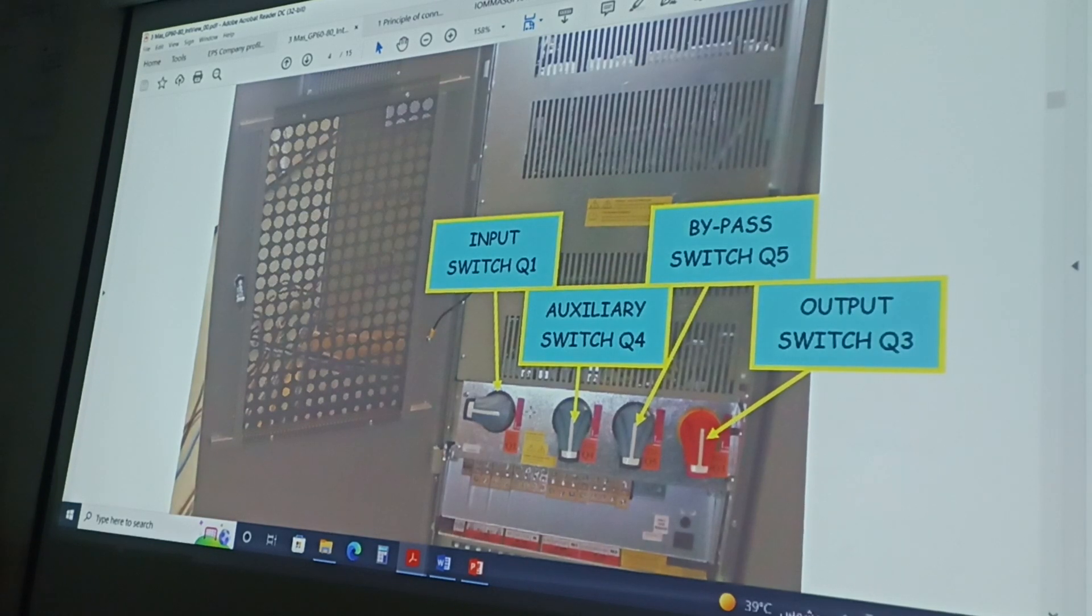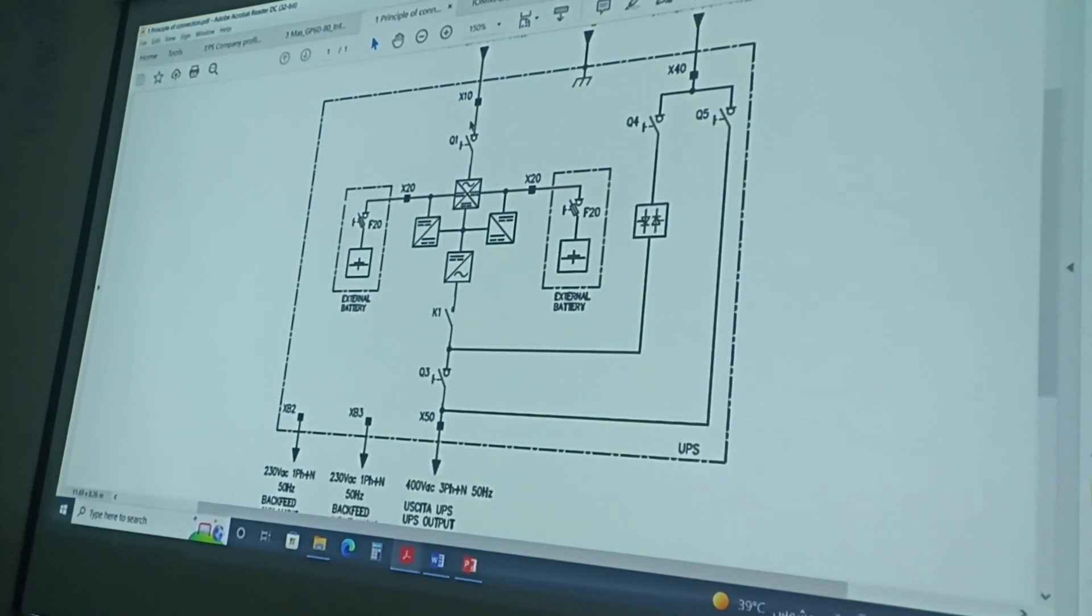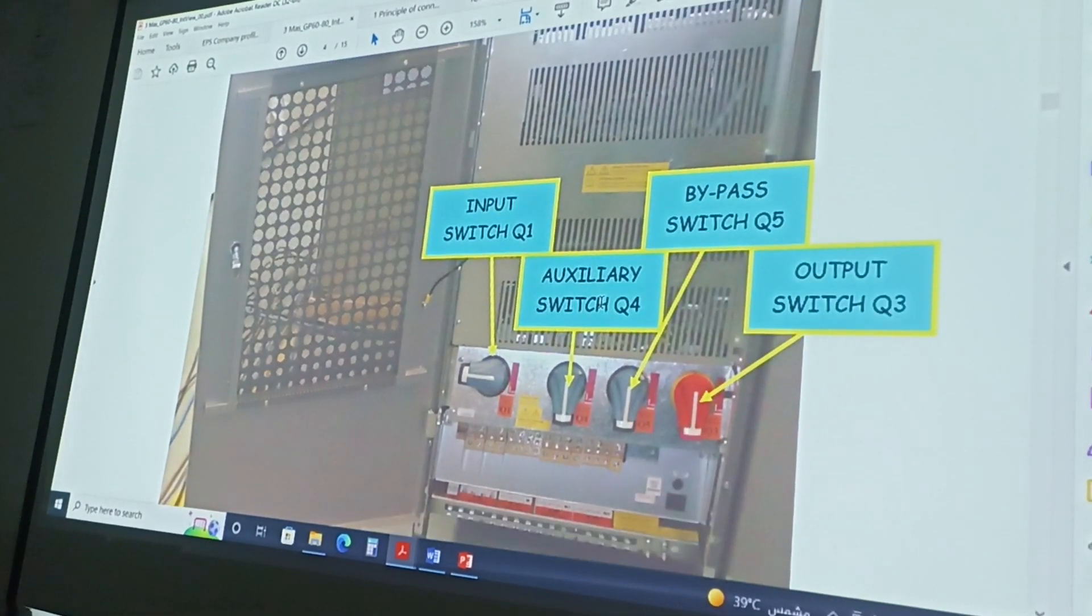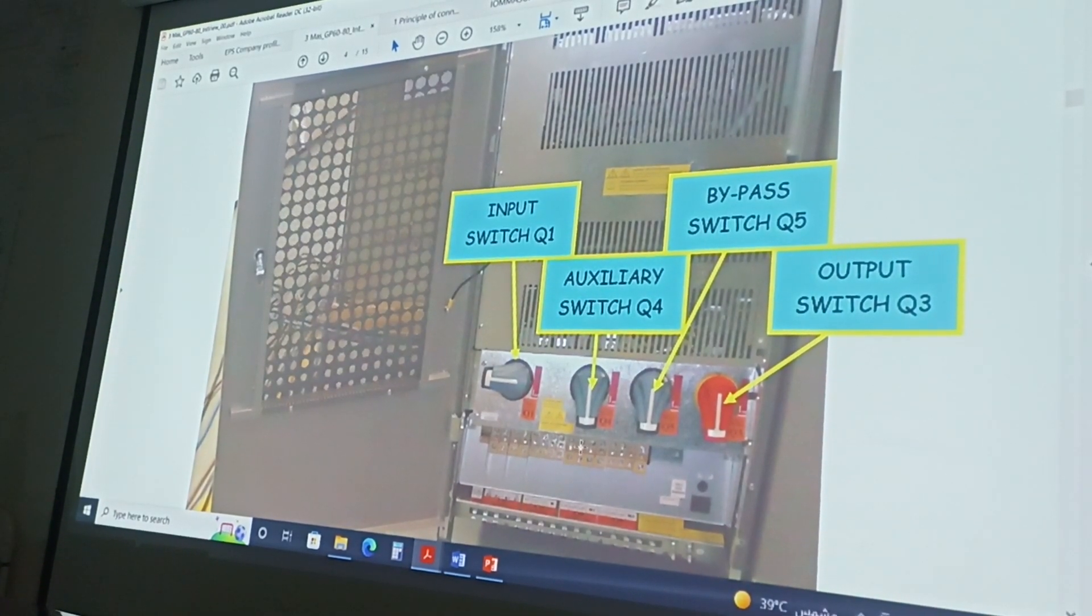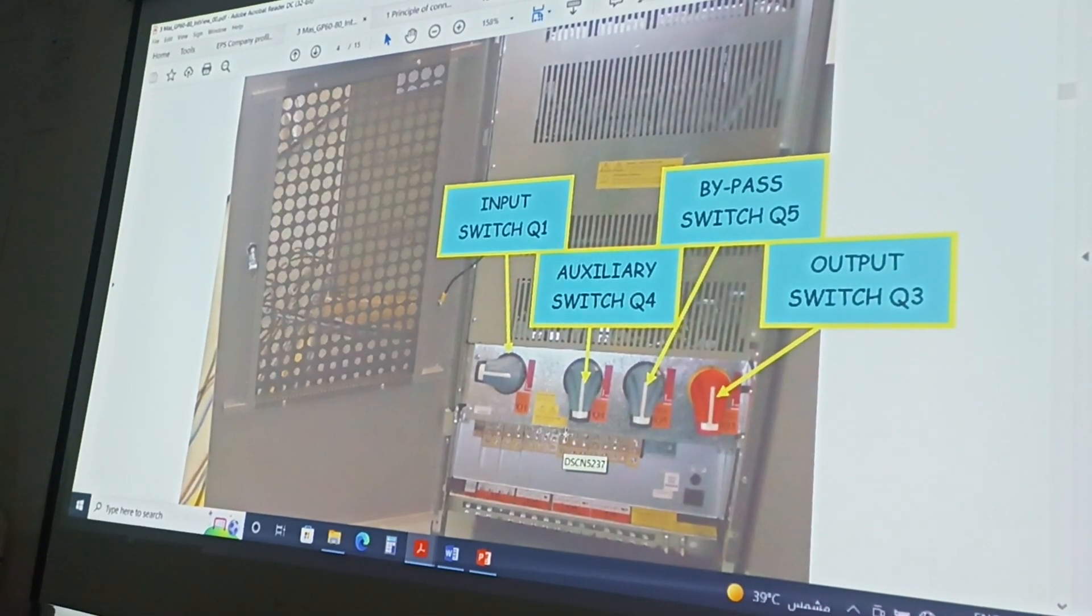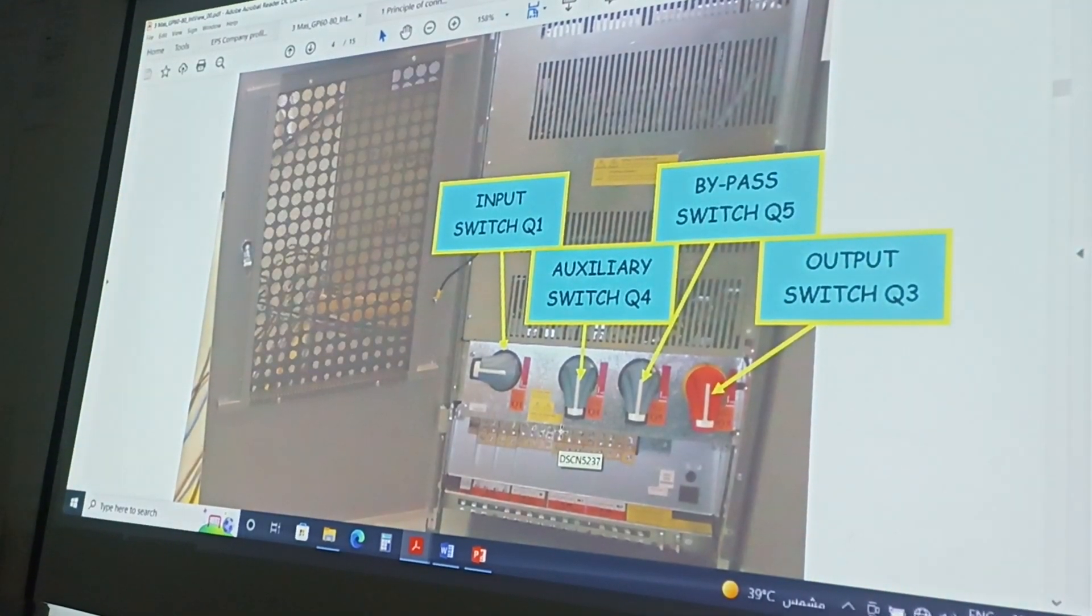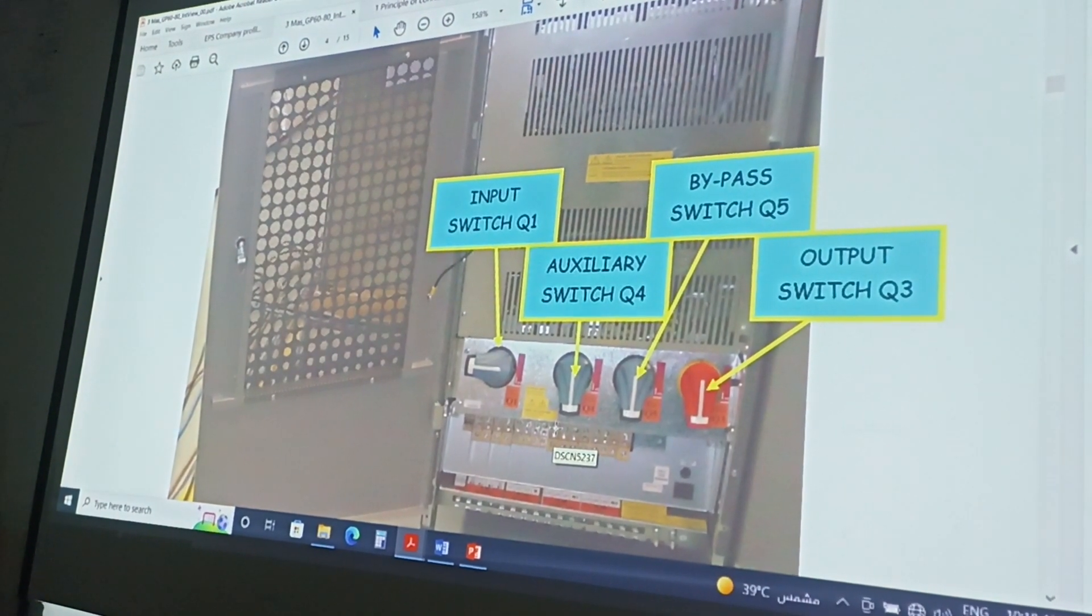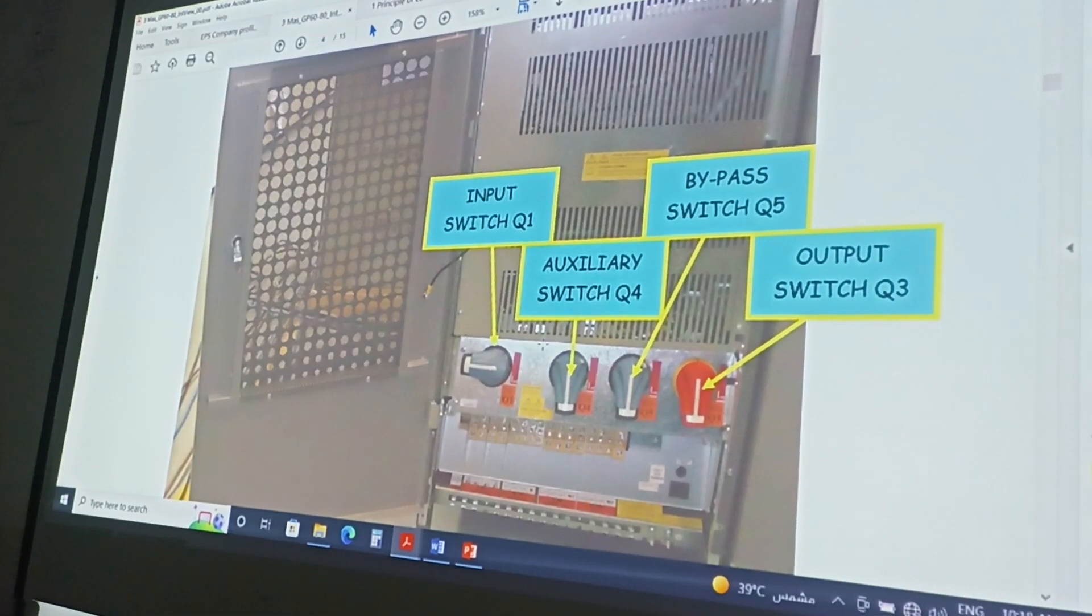Here we have the input switch. This is Q1. This is the auxiliary switch. The auxiliary switch is the input of the bypass. And as we said, in this connection, sometimes we'll put a jumper down in case there was no auxiliary supply or two sources. I mean, usually what would be the connection. We'll take directly from the electrical source, and auxiliary source would be, for example, the generator system, or any auxiliary source. But in case if I have outside only one source, so I would just jumper it.